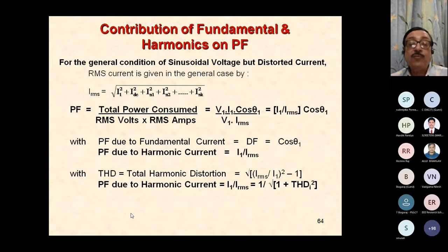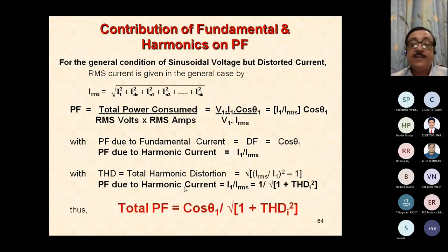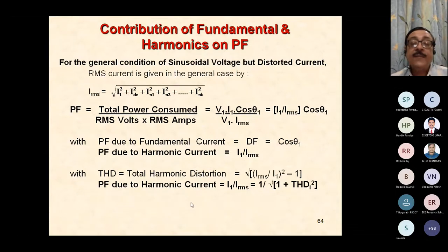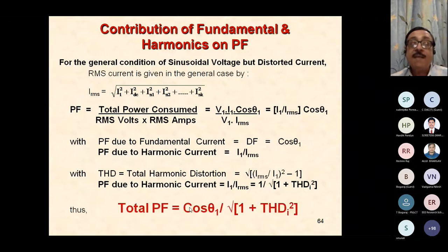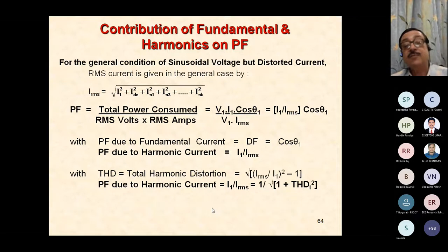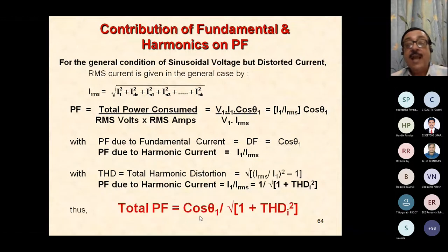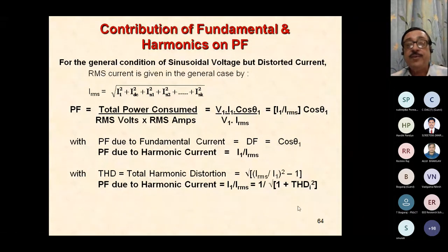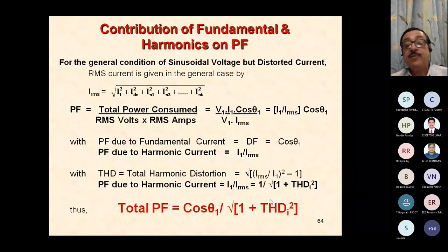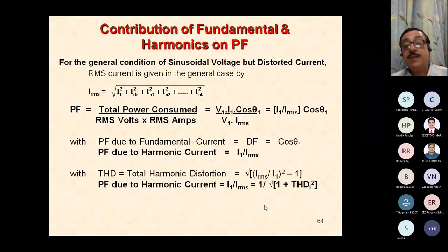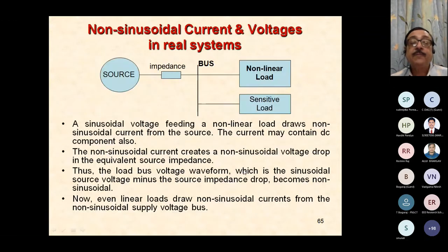So combining together, total power factor is cos theta 1 divided by this, which shows that there are double effects on the power factor. If the fundamental current is having a displacement other than 0 degrees, then the power factor is going to be bad, which is expressed in terms of the numerator. And if the current is going to have harmonics, then also the power factor is going to be bad, which is expressed in terms of the denominator. So both ways, you will have a bad power factor.